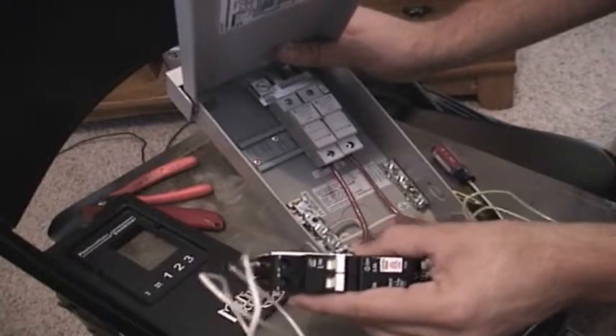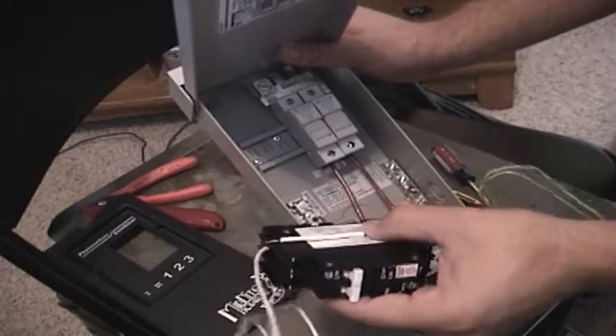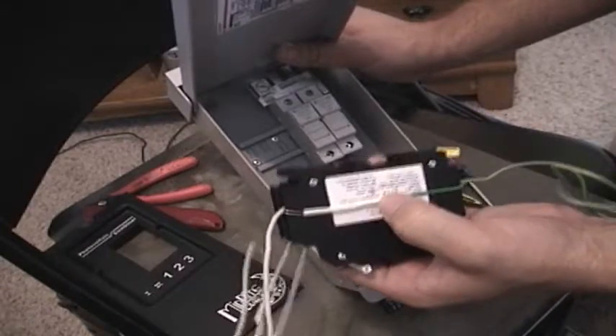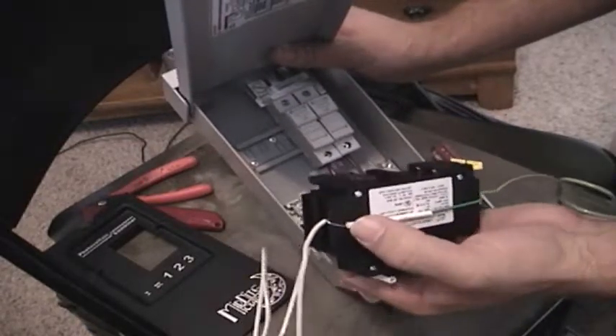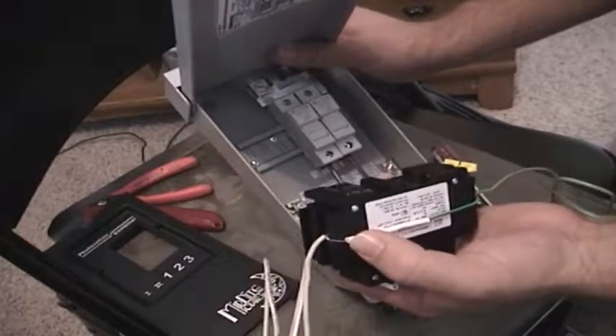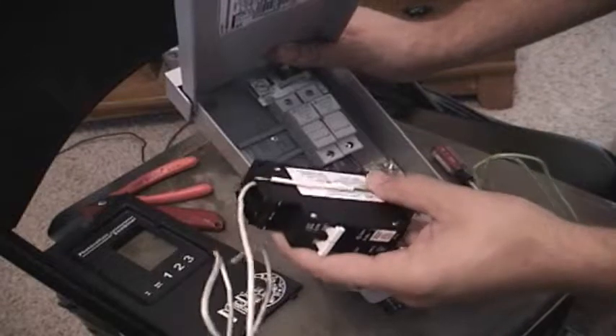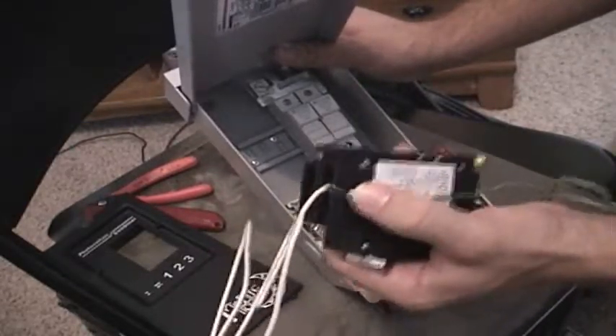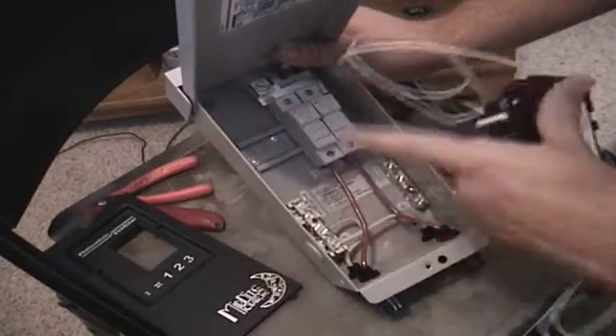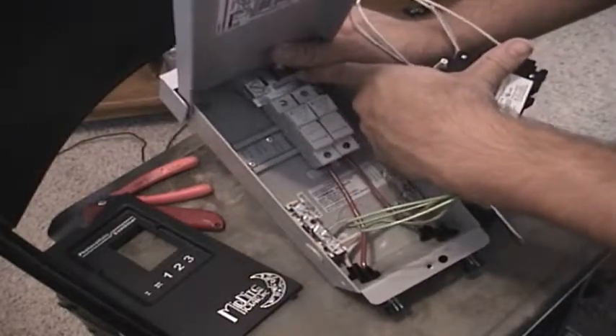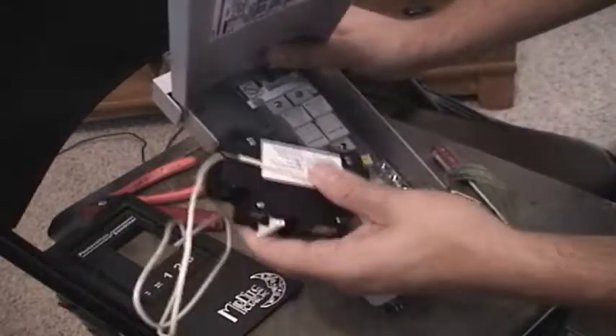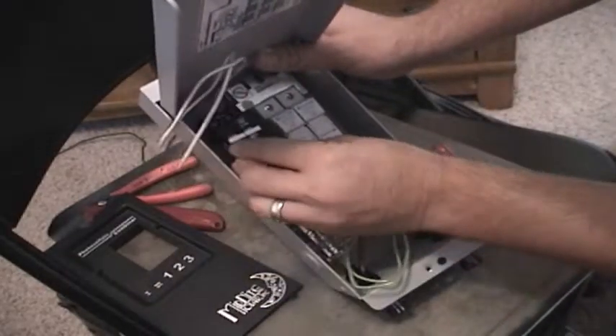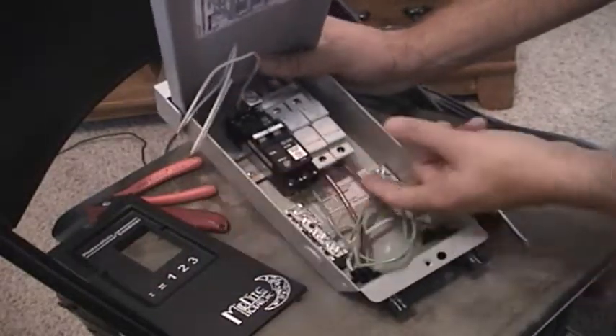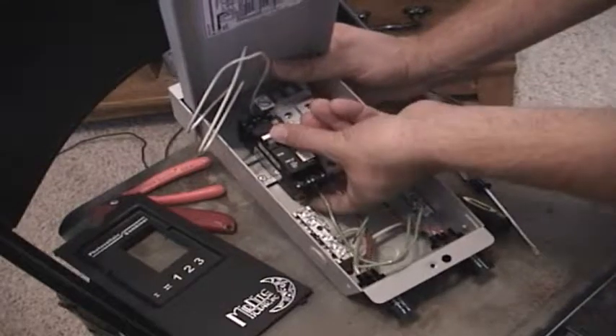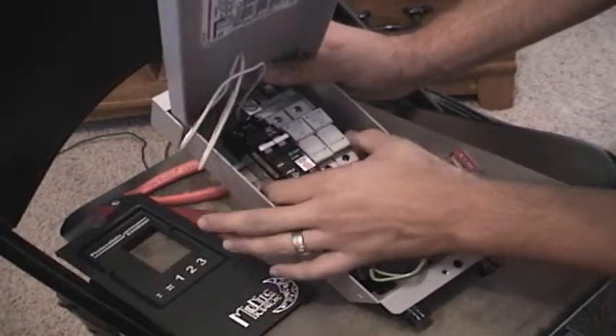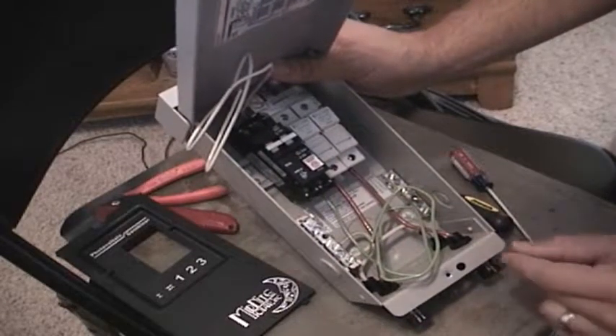We now have plenty of room in our combiner box to install the GFP device. If you will notice, there is a resistor on one side of the GFP device, and that resistor has a leg of bare wire. So when you install the GFP device into the combiner box, make sure that that bare leg of wire is not touching anything, especially the PV out bus bar on the top of the circuit breakers. Let's go ahead and install the GFP device now. Make sure you push in the little yellow tabs on the bottom. Okay, now let's wire it up.